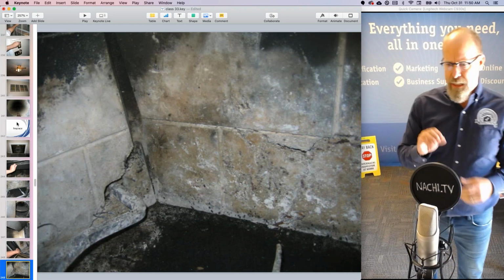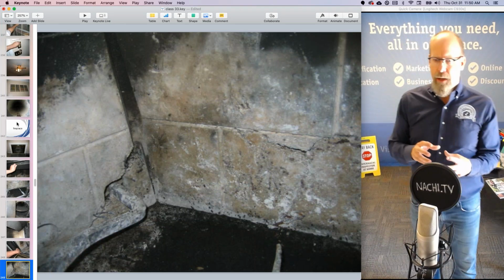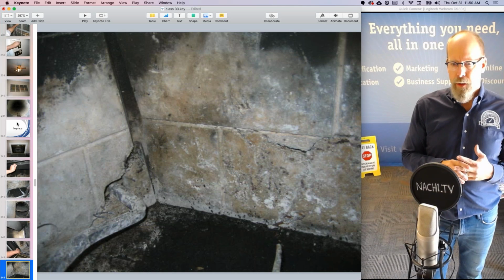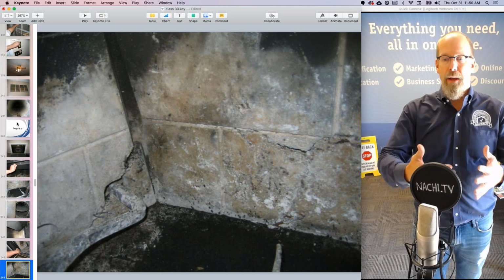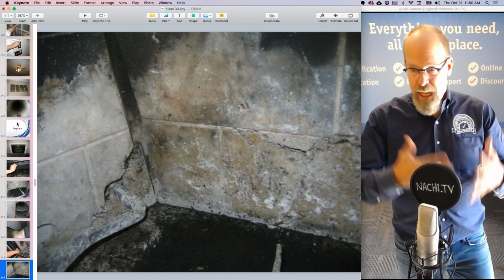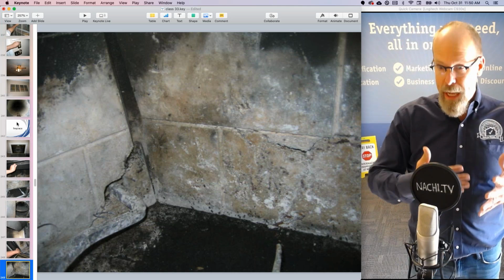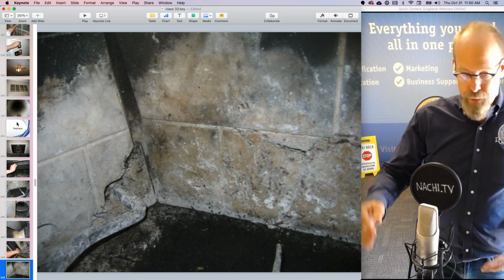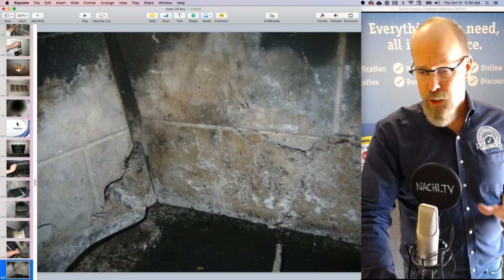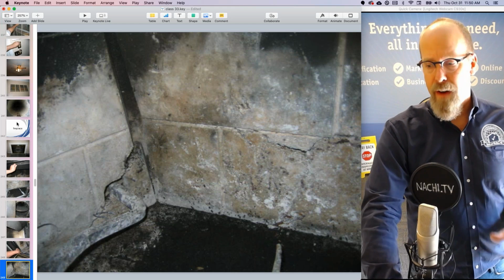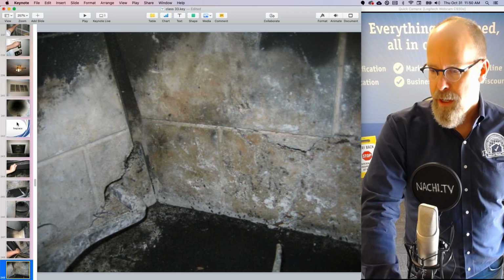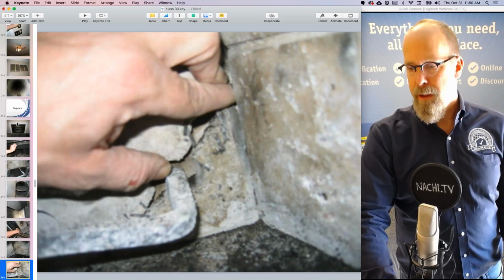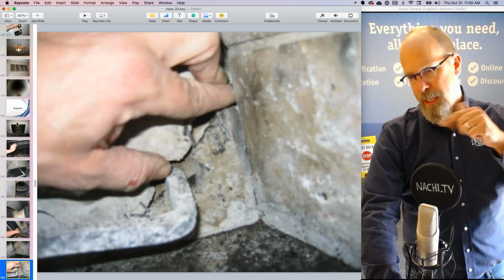So there's significant major damage to the walls of the factory-built fireplace. This isn't a brick fireplace. It's a factory-built fireplace, and those panels can be replaced, and they really need to be replaced. You cannot have breaches in that firewall and have a fire. It'll just catch the chimney on fire. So you're really saving somebody from a fire. You can see there's a lot of damage there.